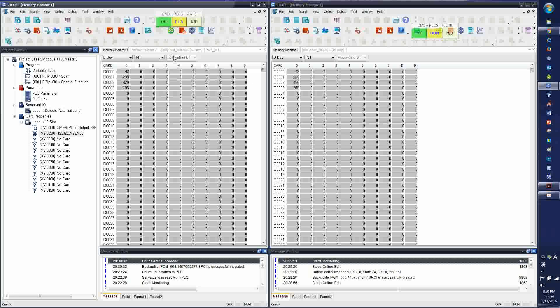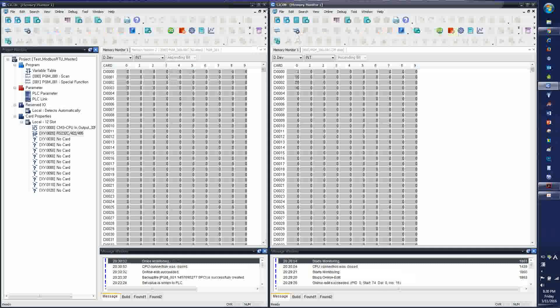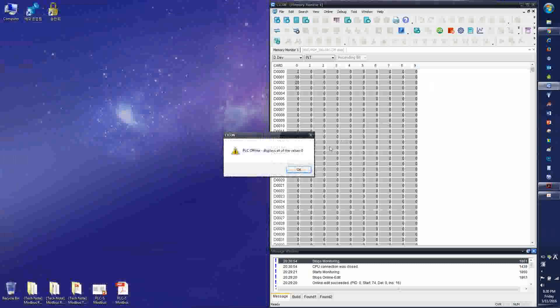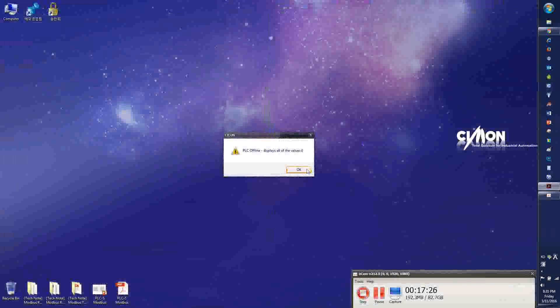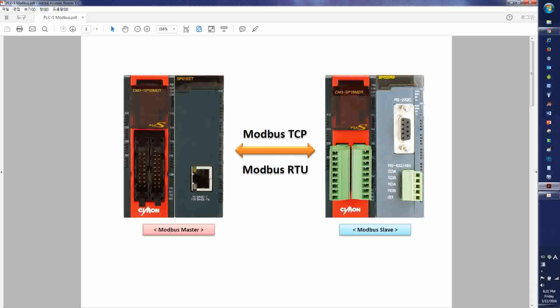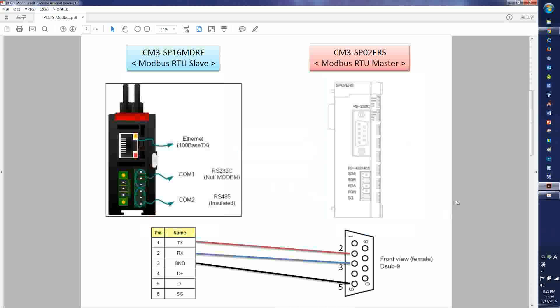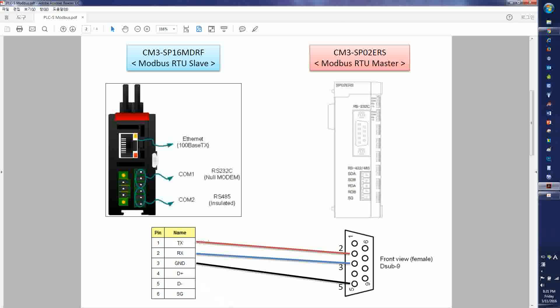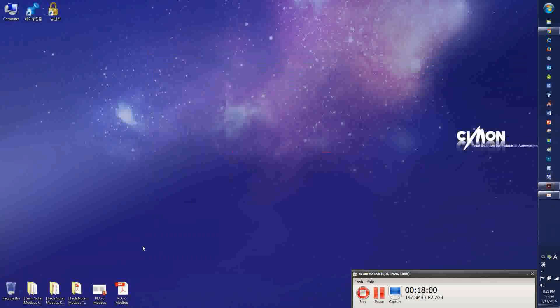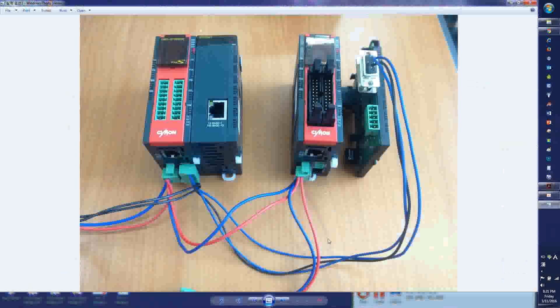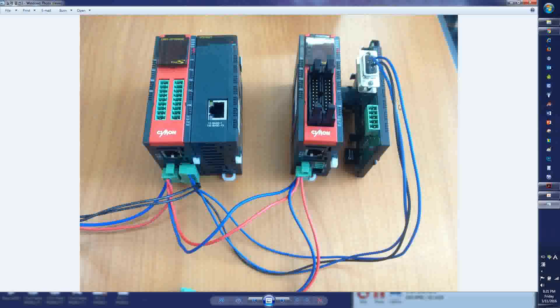Okay, so that was Modbus RS-232. And the wire for the RS-232 is as shown here. My TX goes to the second pin. And my RX goes to the third pin here. And my ground below goes to my fifth pin. So the actual wiring would be like this. The serial module RS-232 to my CPU over here.